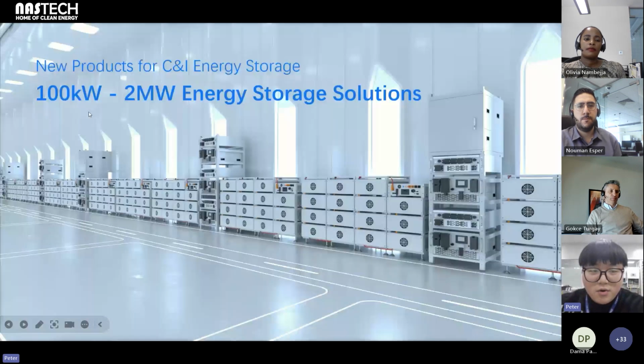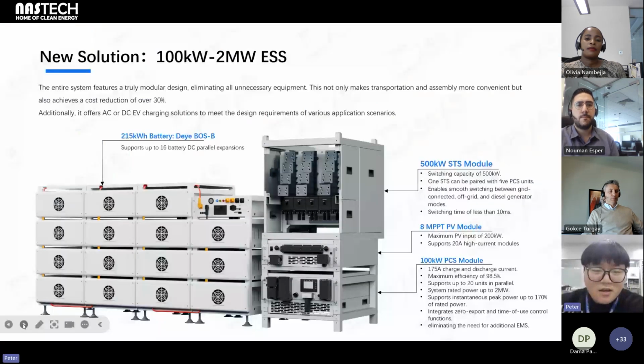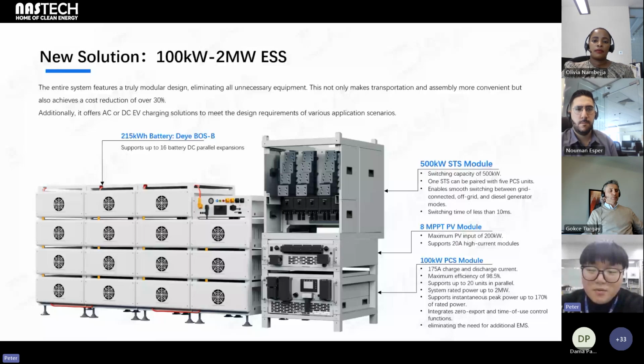And here is a 100 kilowatt system, and it can be paralleled up to a maximum of 2 megawatt. This is the PCS solution, and you can use a 215 kilowatt hour battery. This is a BOS-B solution together with the PCS. The PCS actually has a similar function to a hybrid inverter, but it was designed in different sections. And the STS is 500 kilowatts, so it can be paralleled with 5 PCS together, and each PCS is 100 kilowatt. You also have an MPPT module, which is 8 MPPT. And you can connect in a system like this.